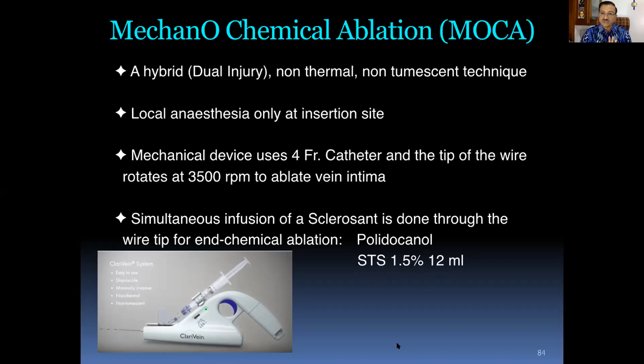The mechanical device uses a 4-French catheter, which is slightly smaller than our one, and the tip of the wire rotates at 3,500 RPM to ablate the vein intima from inside. At the same time, a sclerosant is infused through the wire tip for the end chemical ablation, where polidocanol or STS, both of them can be used in the concentration of 1.5%, and this is the quantity. We'll quickly see a video of this.